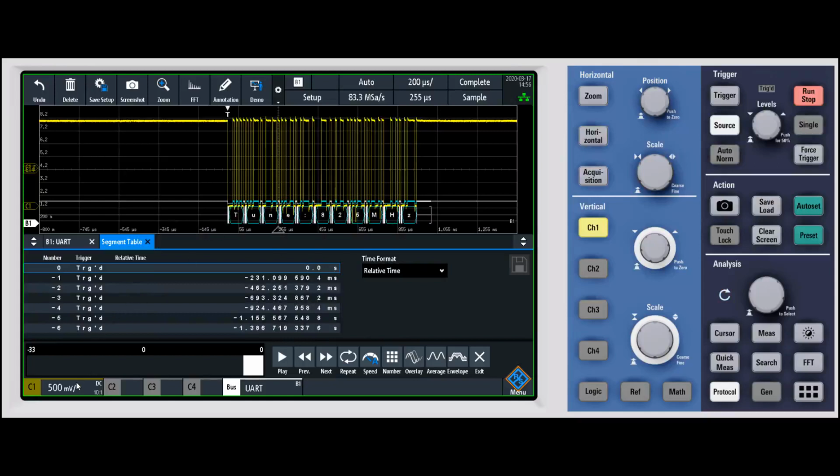The other thing, if you look down at the bottom, each of the channels, if you click on them, it'll pop up the menu for it. So in this case, I have a 1 megohm probe plugged on, so it won't allow me to change it. But if we didn't have that, we could change between a 50 ohm input and a 1 megohm input. You can change between AC and DC coupling. You can turn on the different bandwidth controls. We can go into the probe menu, etc.